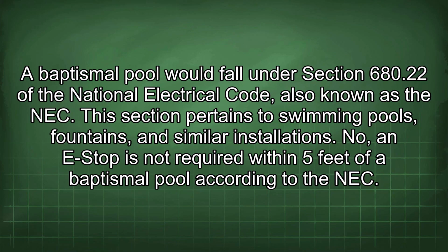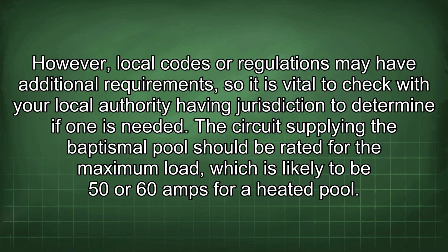A baptismal pool would fall under Section 680.22 of the National Electrical Code, also known as the NEC. This section pertains to swimming pools, fountains, and similar installations. No, an e-stop is not required within 5 feet of a baptismal pool according to the NEC. However, local codes or regulations may have additional requirements, so it is vital to check with your local authority having jurisdiction to determine if one is needed.